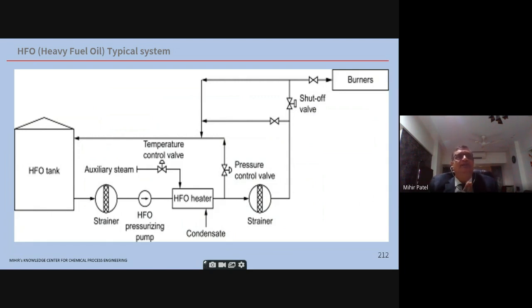So that's why the HFO system is kept at a minimum temperature, maybe 100 degrees, maybe 120 degrees, depending on the fuel oil. One has to keep the centistokes, and then you decide the temperature. So in the fuel oil tank, you will have steam heating also, although not shown here. Then the HFO pump is there. You have an outlet, there's a heater where you are putting, let's say, steam and condensate, so that you are heating this basically. Then you have strainers. Now this entire system, please take note in the diagram, is continuously kept in circulation.